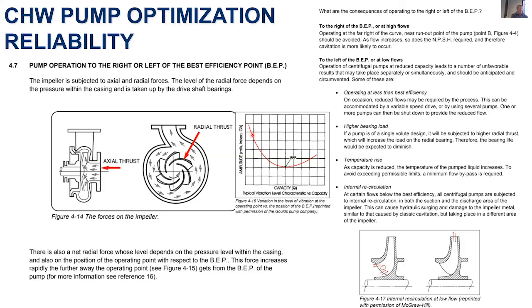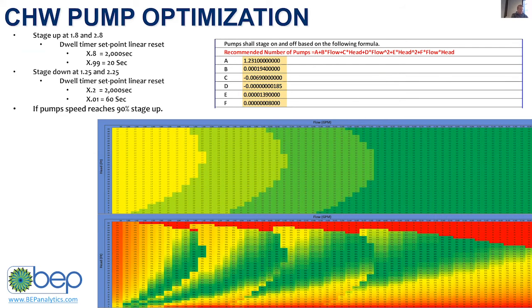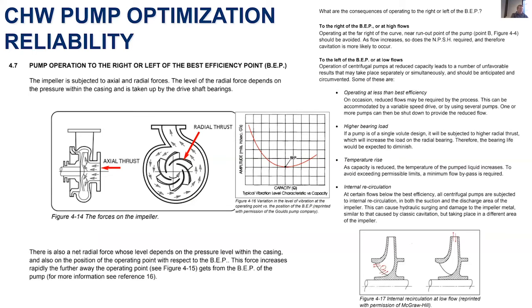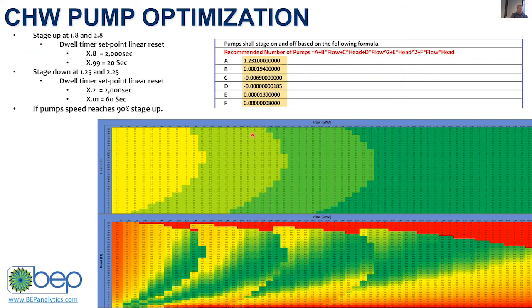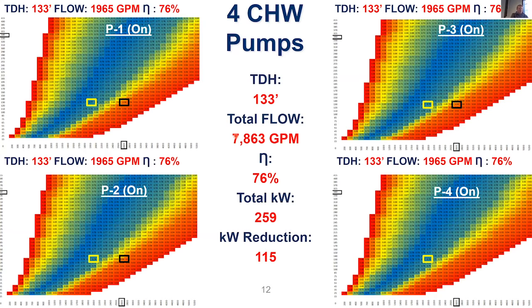Go out to your pumps and make sure you're doing the same conditions. The important thing is, if you turn the 4th pump on, did your flow increase or did your head change? Turn on the 4th pump and get it back to the exact same conditions, so you've normalized your little experiment. Then see, did the power go up or did the power go down? If the power went up, you moved it too far to the left. And you can look at the pump curve beforehand, before you even try that experiment.